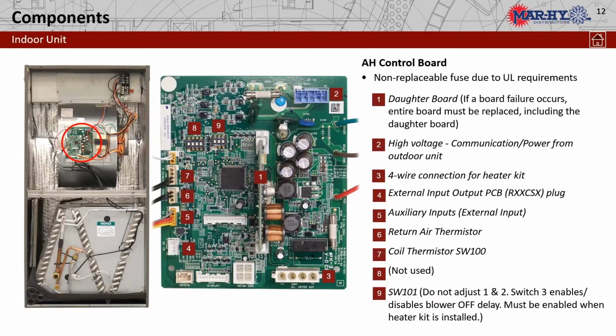This is that auxiliary PCB. This would be the plug-in to connect to that auxiliary board. Then we've got 5, which is auxiliary inputs. 6 is our return air thermistor. 7 is our coil thermistor. 8 not used.